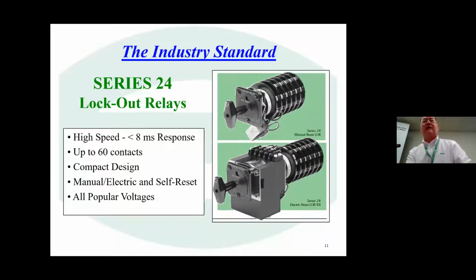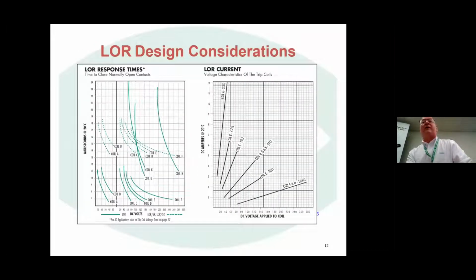So as I look at lockout relays and make my selections, one of the things that I want to be conscious of, and utilities are very conscious of, is the response time for the fastest operation of a lockout relay and the range that the coil can handle and operate within. And so many utilities specify coils that give you a nominal value, but may fall into a lower current range or a lower voltage range that allows that trip coil to operate closer to their sweet spot, if you will, of how they may have under or over voltage conditions in their particular substations.